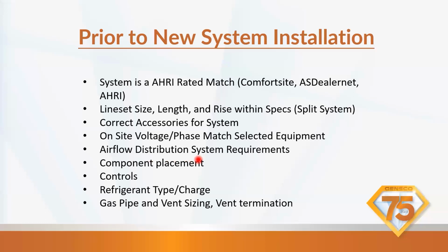We want to make sure that we have airflow distribution system requirements. So we want to make sure that the ductwork is in good standing order and it's sized correctly. That could be a challenge in a lot of retrofit applications. Component placement, we want to make sure there's no obstructions, no landscape, no garbage cans set right in front of the unit to affect the airflow and whatnot. We want to confirm that we have the proper controls, the refrigerant type and charge. Everything's mostly 410A right now, but we are coming to a transitional refrigerant type change, which we'll have classes on in the near future to get you guys all ready on the A2L stuff. But this is going to come into play. You're going to have to be aware of what refrigerant we have in.